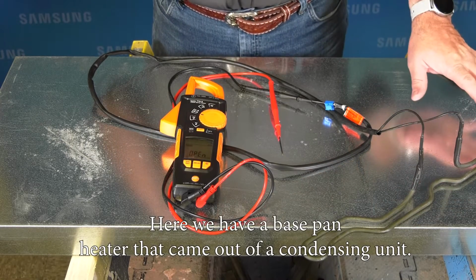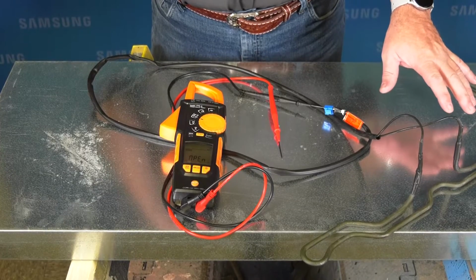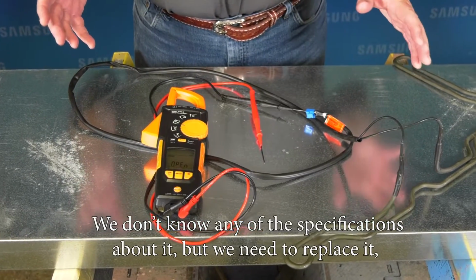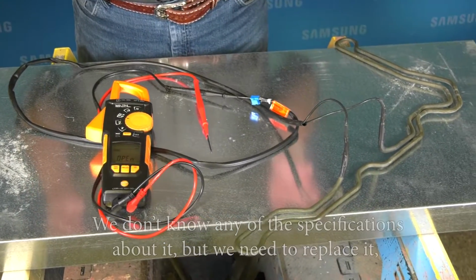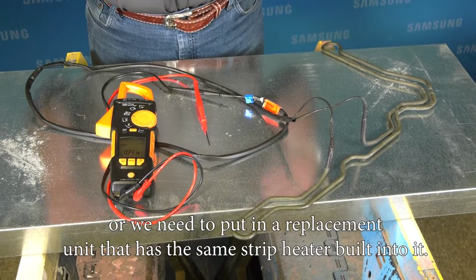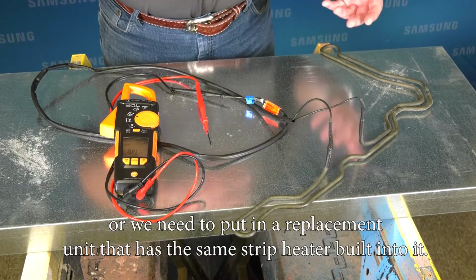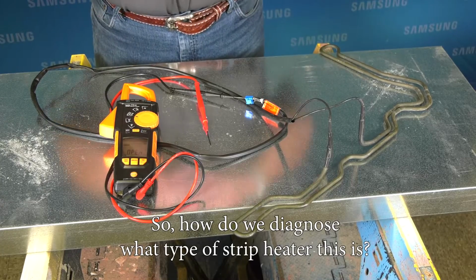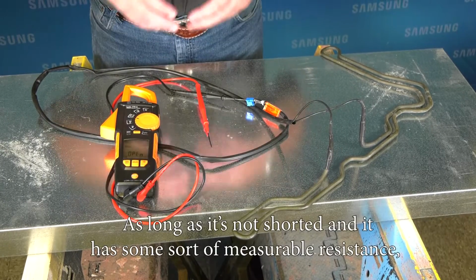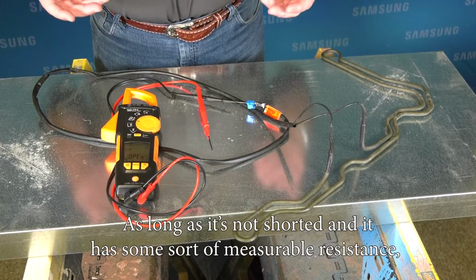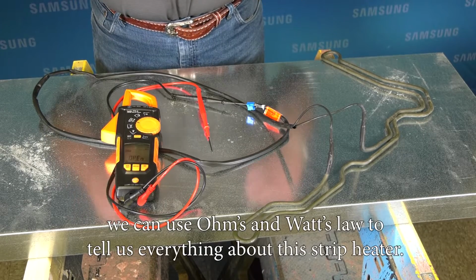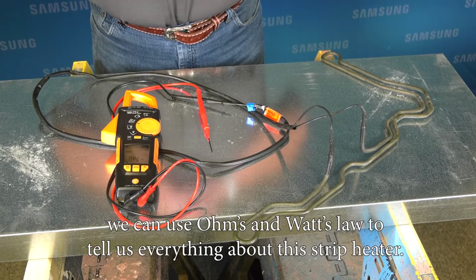Here we have a base pan heater that came out of a condensing unit. We don't know any of the specifications about it, but we need to replace it, or we need to put in a replacement unit that has the same strip heater built into it. So how do we diagnose what type of strip heater this is? As long as it's not shorted and it has some sort of measurable resistance, we can use Ohm's and Watt's Law to tell us everything about the strip heater.